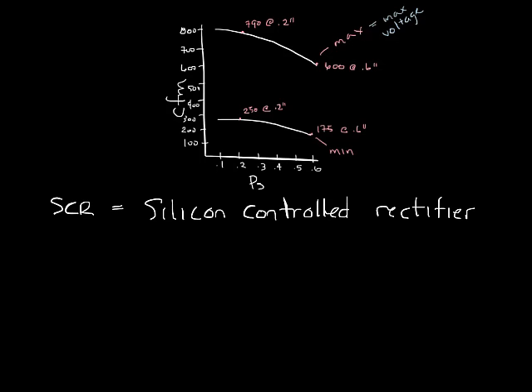I won't go into the details of the SCR. You can look that up online or maybe on wiki. But basically the SCR is a voltage chopper. By turning down the SCR in a fan box you send a lower voltage to the motor which slows it down and lowers the CFM of the fan box.